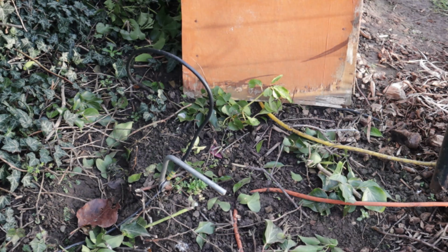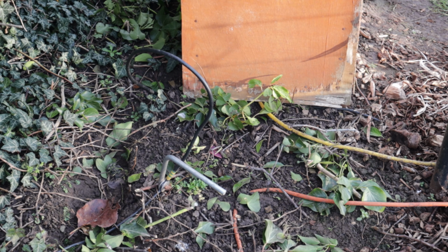So here's my sneaky tip to make your earth spike work more efficiently. If you can see that sort of L-shaped piece of metal that's hammered well in, there's 3 foot of that underground. First thing to note is that's a commercial earth spike, and they do work well, and one advantage they have is they're generally corrosion resistant - that's been in for a number of years, not a bit of rust on it. And you can see the black cable leading out from underneath the box connected to the earth spike.